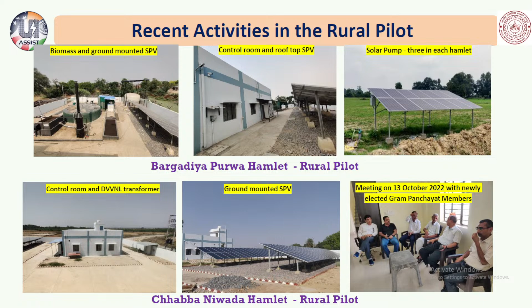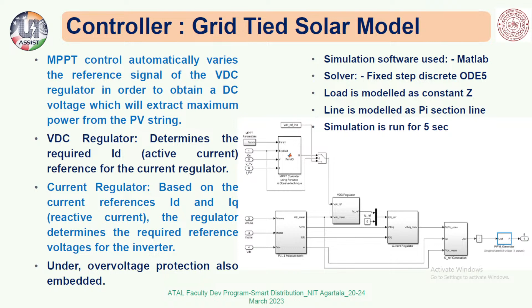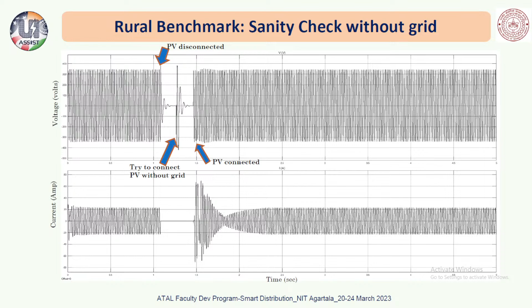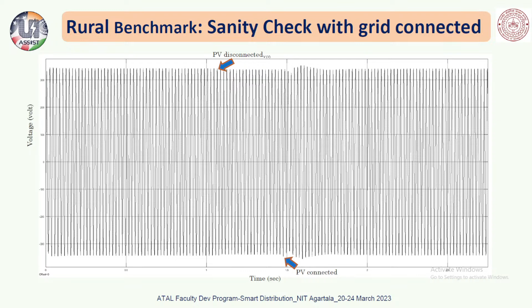I'll skip that, because before setting up we did a lot of simulations. We designed the converter, and this is the rural main distribution system. We simulated both in real time and on MATLAB, and then designed the controls already implemented at the site, like DC voltage control, where the DC regulator gives the active current reference, and the current regulator gives the command to the inverter voltage reference point. Under-voltage and over-voltage protection were also verified. Then we did a sanity check: if the grid is not there, PV is the only source, so if PV is present, current flows, otherwise it's zero. If it's grid-connected, nothing happens to the voltage there. So after verifying everything, we went ahead.